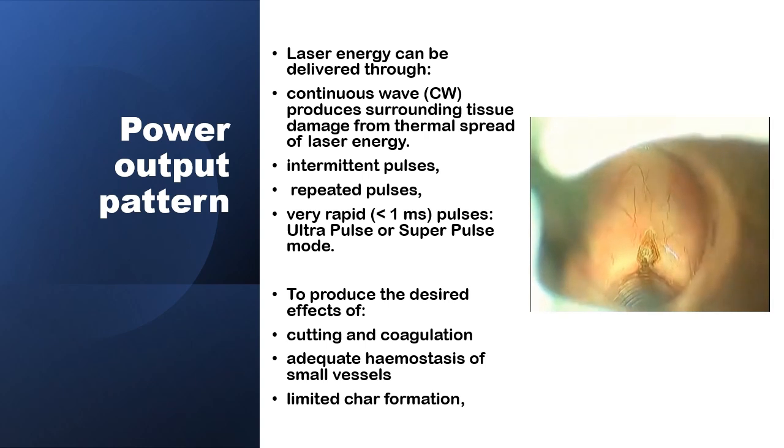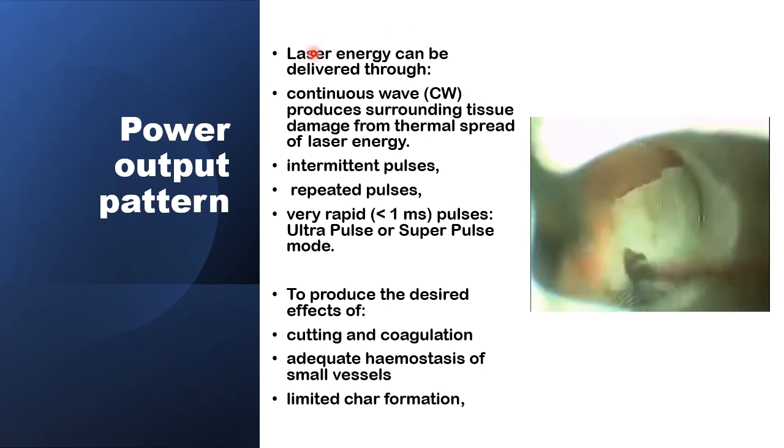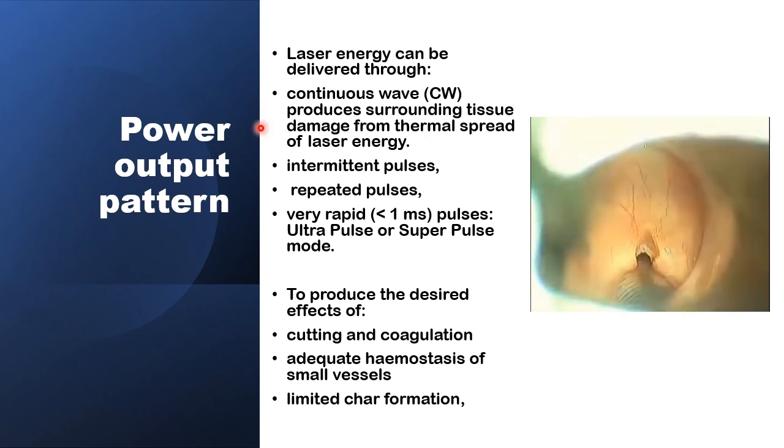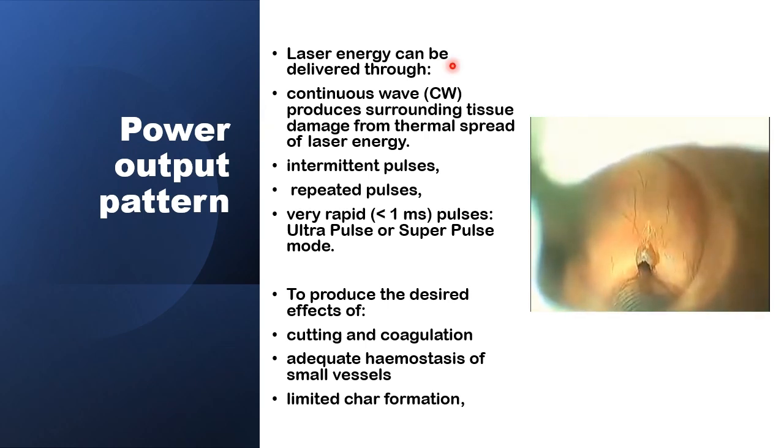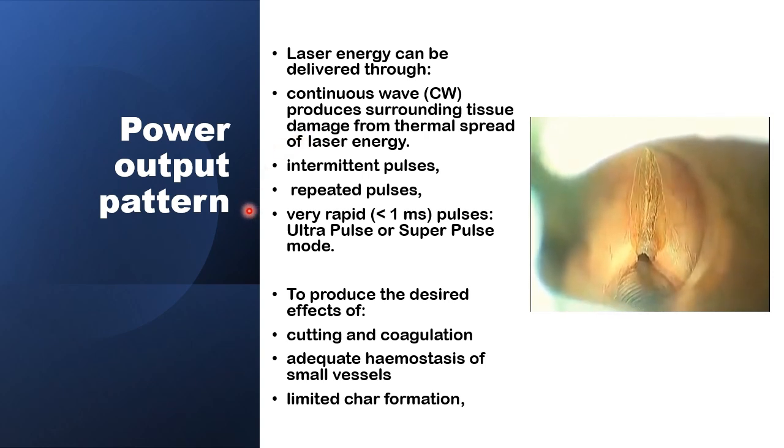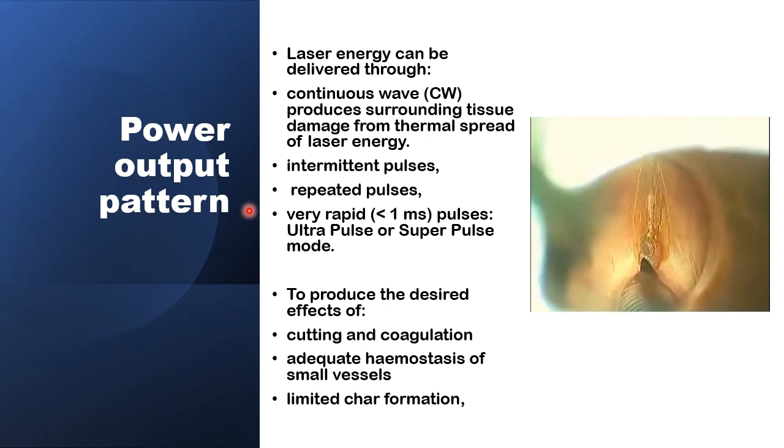So far we have been through how the surgeon would choose a certain amount of energy or power, and also specify a length of the cut and suggest a certain depth and the time on and the time off. But there are other adjustable parameters that the surgeon would have to specify, and this is how the power pattern, the output pattern, would be.